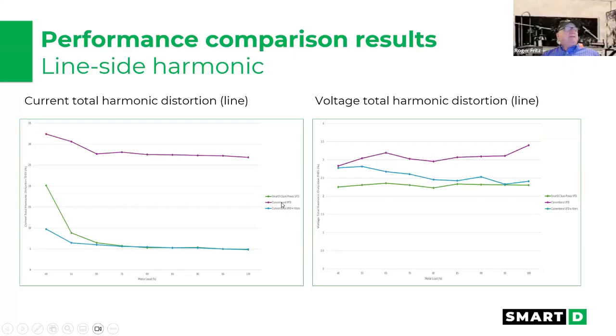So you'll see with the active front end type, with all the filters, they are dropping it down here, very close to what we're doing on the input also, at the load of the motor that we're setting here, at roughly about 5% total distortion. And then on the voltage side, this is a very strong source out there, and you'll see that the conventional can ramp up to about 3.5% voltage. But the power companies on the IEEE 519 want it at or near 5% or less. And so that's what they're doing to get it there.